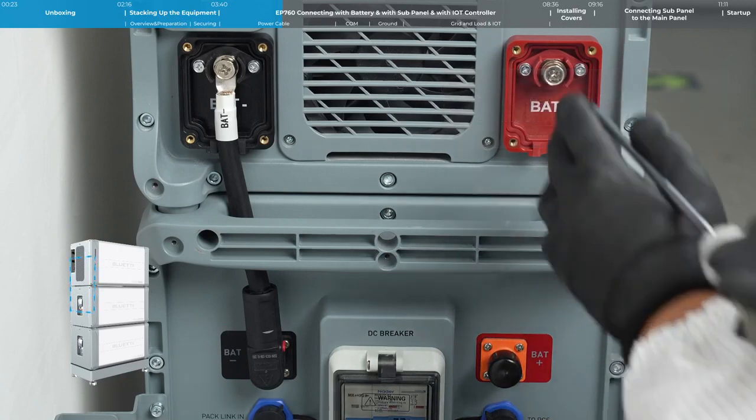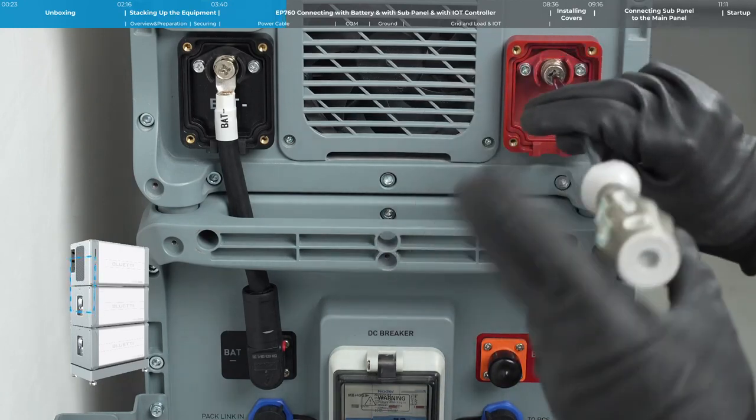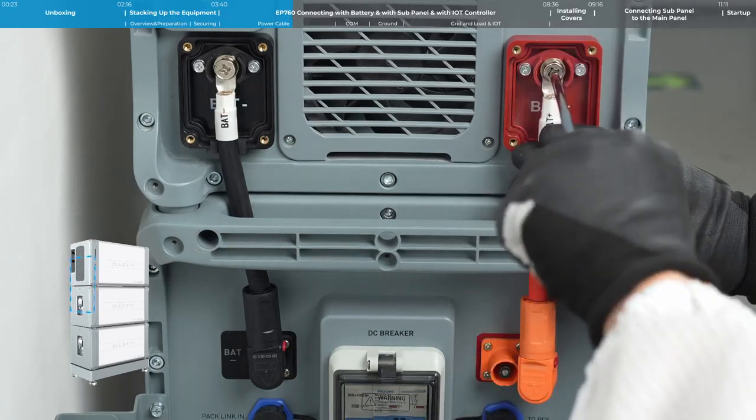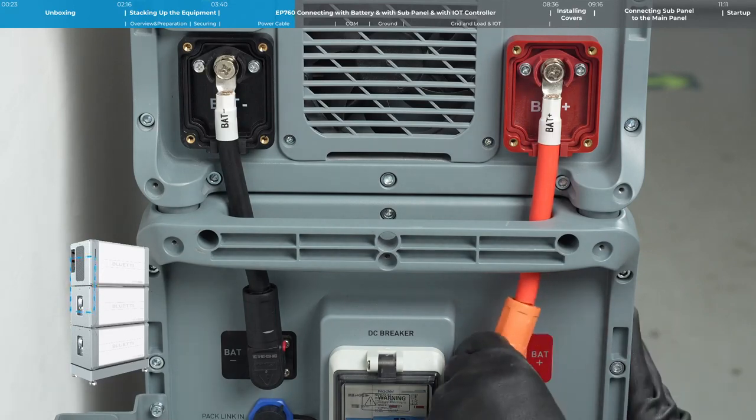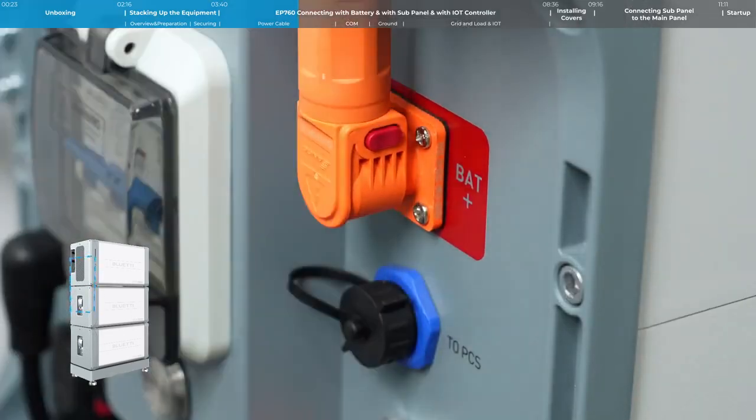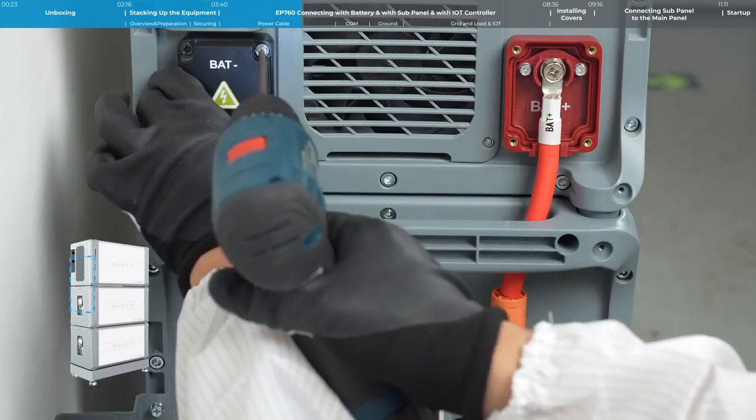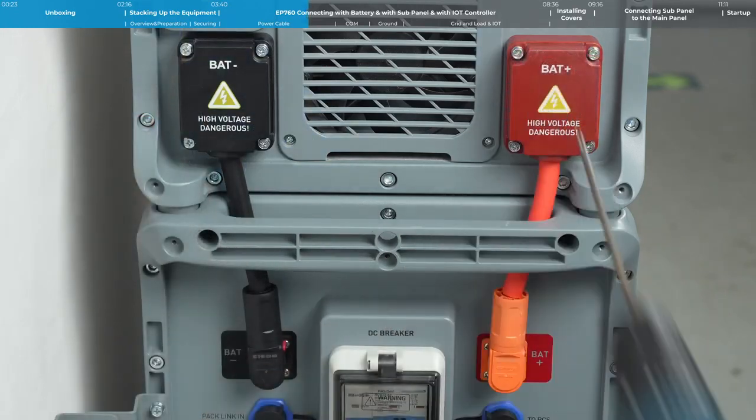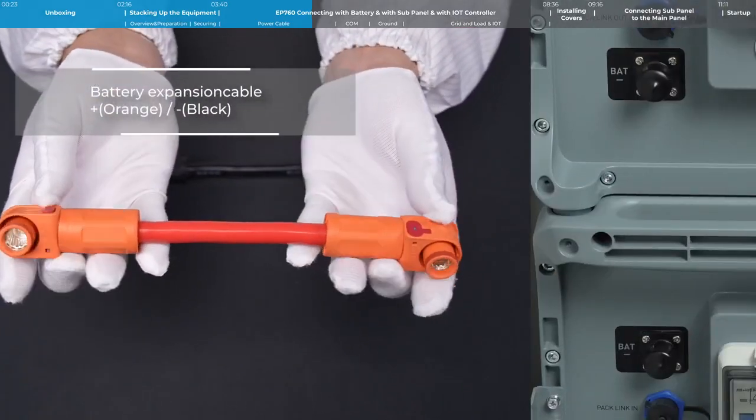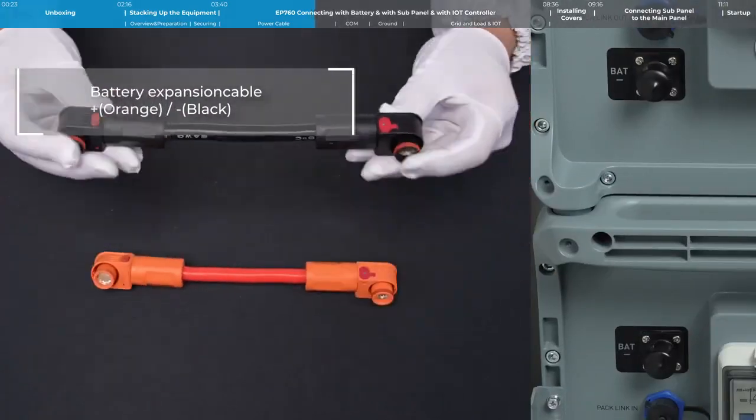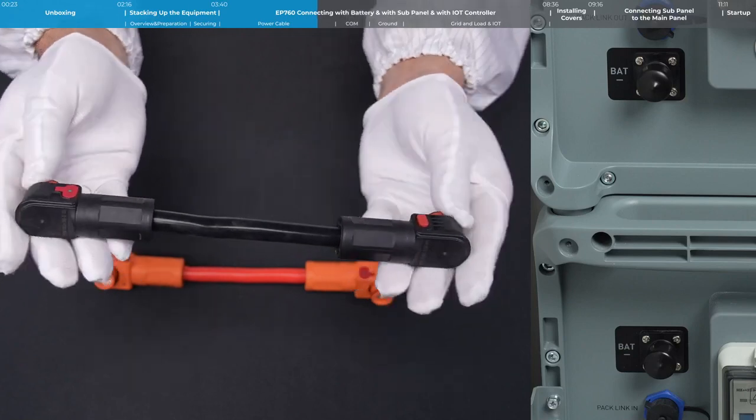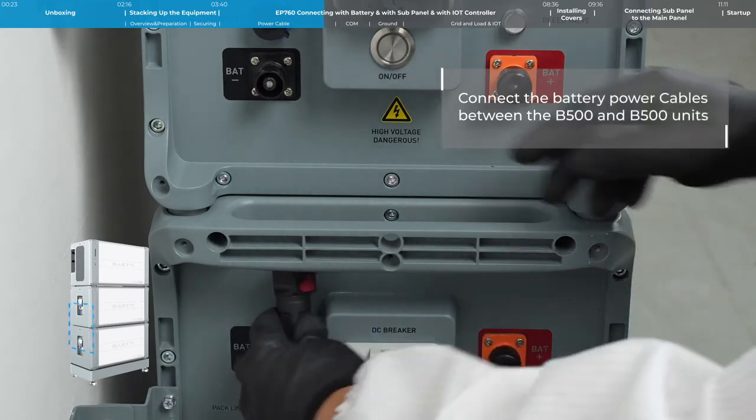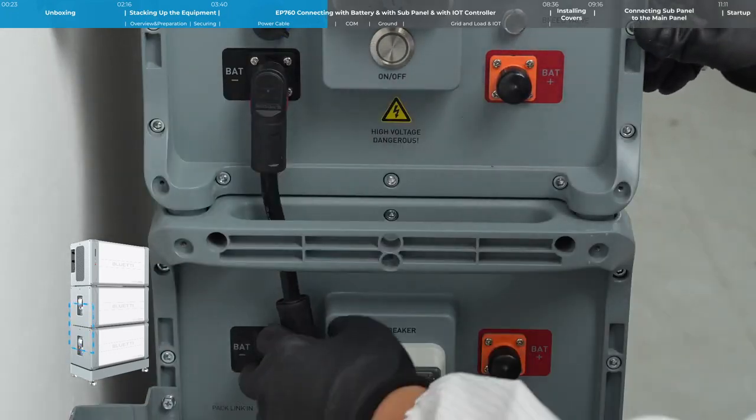Connect the battery power cables between the EP760 and B500 units. You'll hear a click when the connection is properly secured. Once connected, put those protective covers back on. For the battery expansion cables connecting B500 units, both ends of the cable have a quick release structure. Connect the battery expansion cables between the B500 units. You'll hear a click when the connection is properly secured.